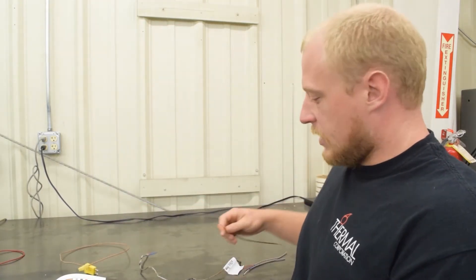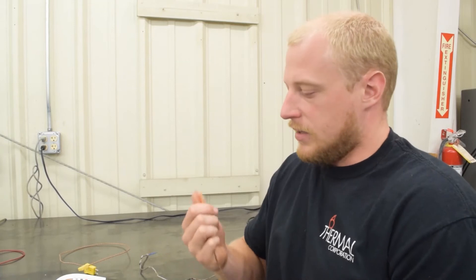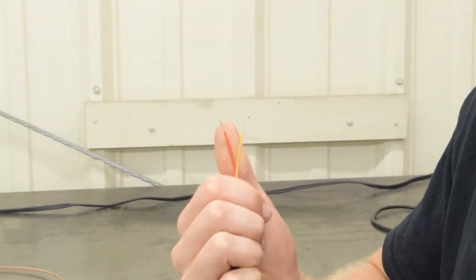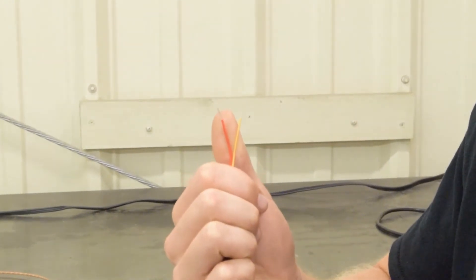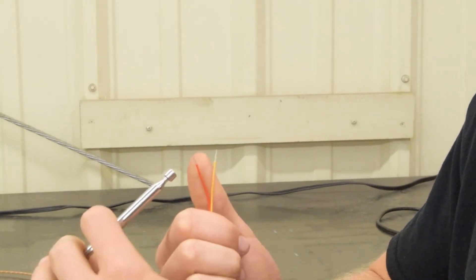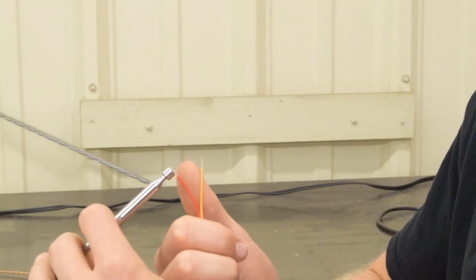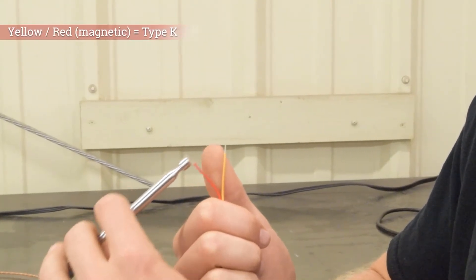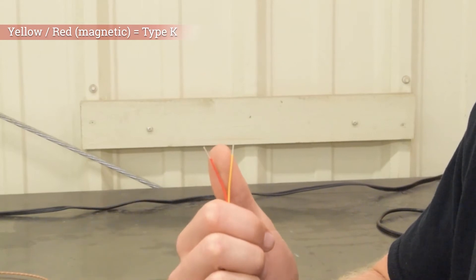Now the other indicator if it doesn't have a plug is lead color. So this is yellow. You can see we have a yellow lead and a red lead here on this thermocouple wire. And the yellow is not magnetic but the red is magnetic. So that is a type K wire and the negative lead or the red lead is magnetic.